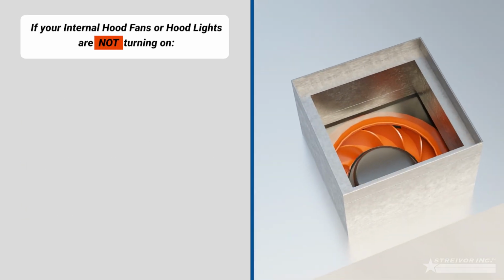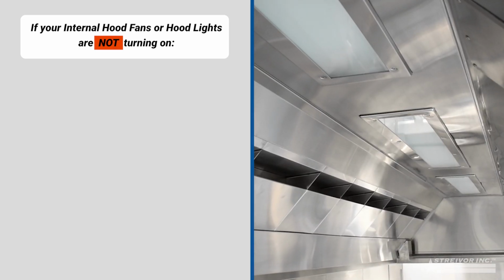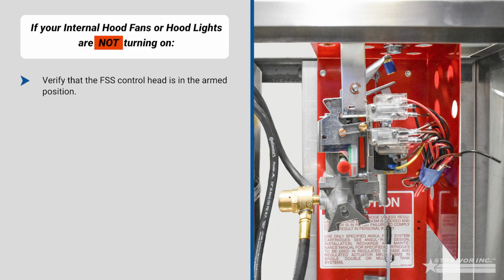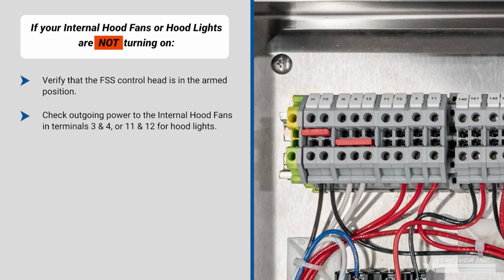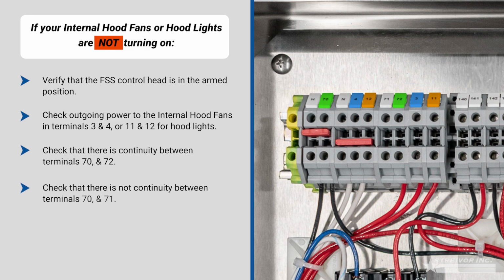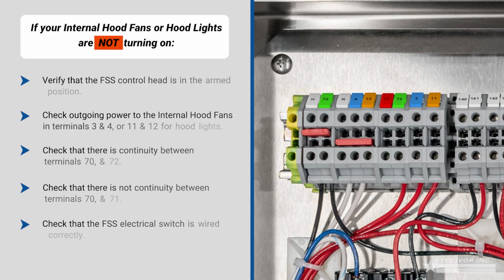If your internal hood fans or hood lights are not turning on, verify that the FSS control head is in the armed position. Check outgoing power to the internal hood fans in terminals 3 and 4, or 11 and 12 for hood lights. Check that there is continuity between terminals 70 and 72. Check that there is not continuity between terminals 70 and 71. Check that the FSS electrical switch is wired correctly.